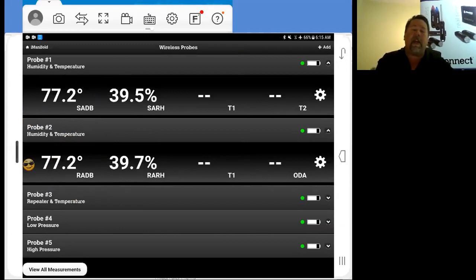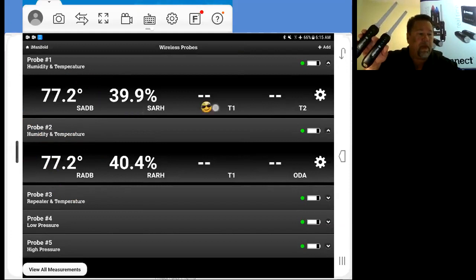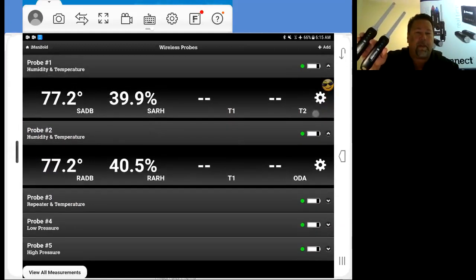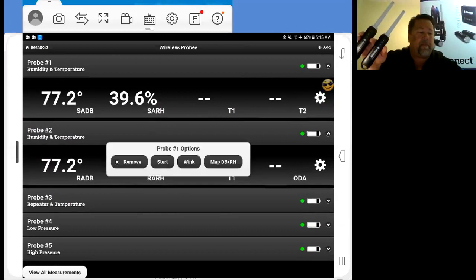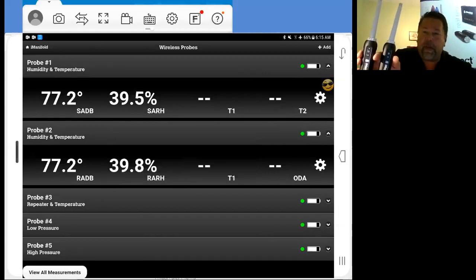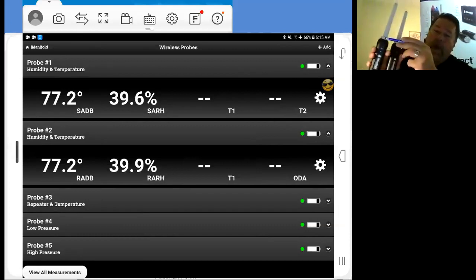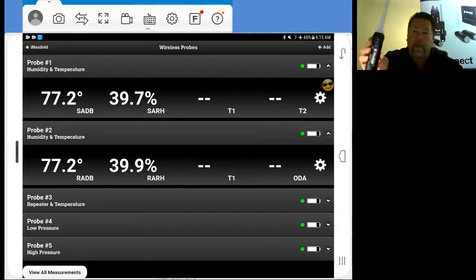If you want to go ahead and identify your probe, put them both in your hand. And we'll take probe number 1. We'll go here to this gear menu on the probe itself. We'll open that up. Now, as you can see, you've got a few selections on there. Remove, start, wink, and map. Mapping, the shortcut is just to touch the temperature. Now, if you want to wink a probe, this is probe number 1. We're going to wink. And we'll take a look here and see which one is which. And as you can see, this probe right here, the light's blinking very quickly.